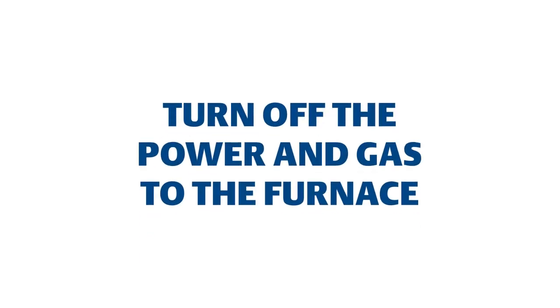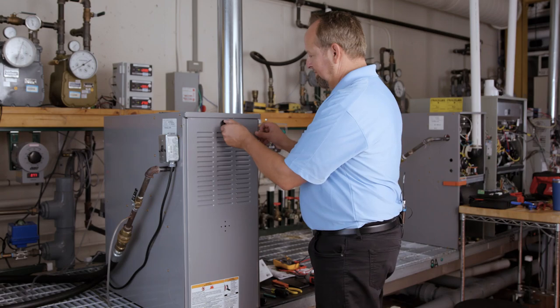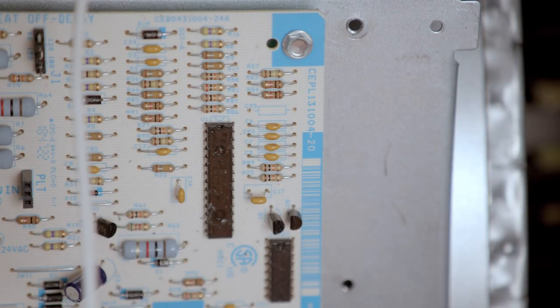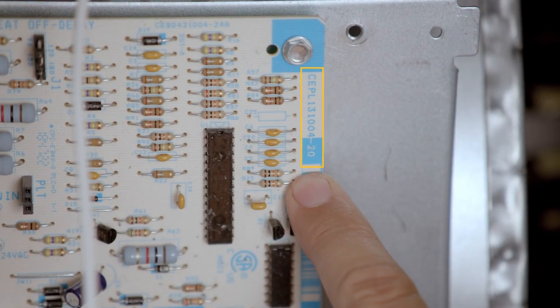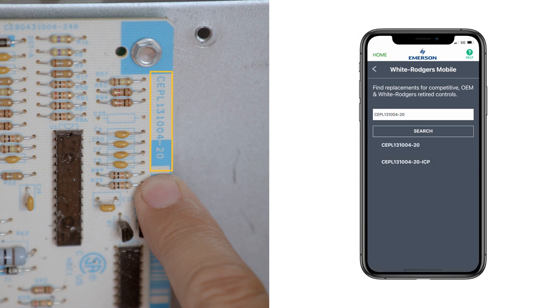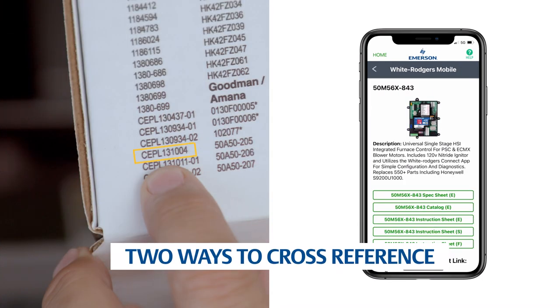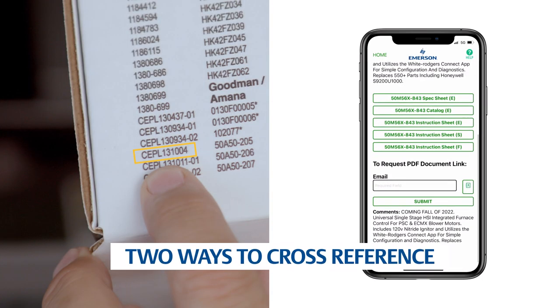First, ensure power and gas are disconnected prior to servicing the unit. Remove the unit access panel. Check the part number on the existing control and verify it as one of the more than 550 modules that can be replaced with the 50M56x843. Use the cross-reference chart on the side of the carton or the White-Rodgers mobile app.